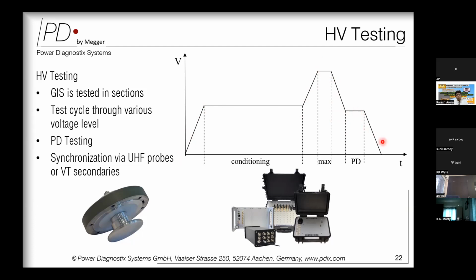During this measurement or PD measurement, it is very important that the synchronization should have been done to the supply voltage or the operating voltage, because if you measure partial discharge data and if it is not synchronized with the phase, then you will not get a proper PD pattern, because as we know, PD pattern is nothing but a PRPD waveform, which is like phase resolved partial discharge pattern.